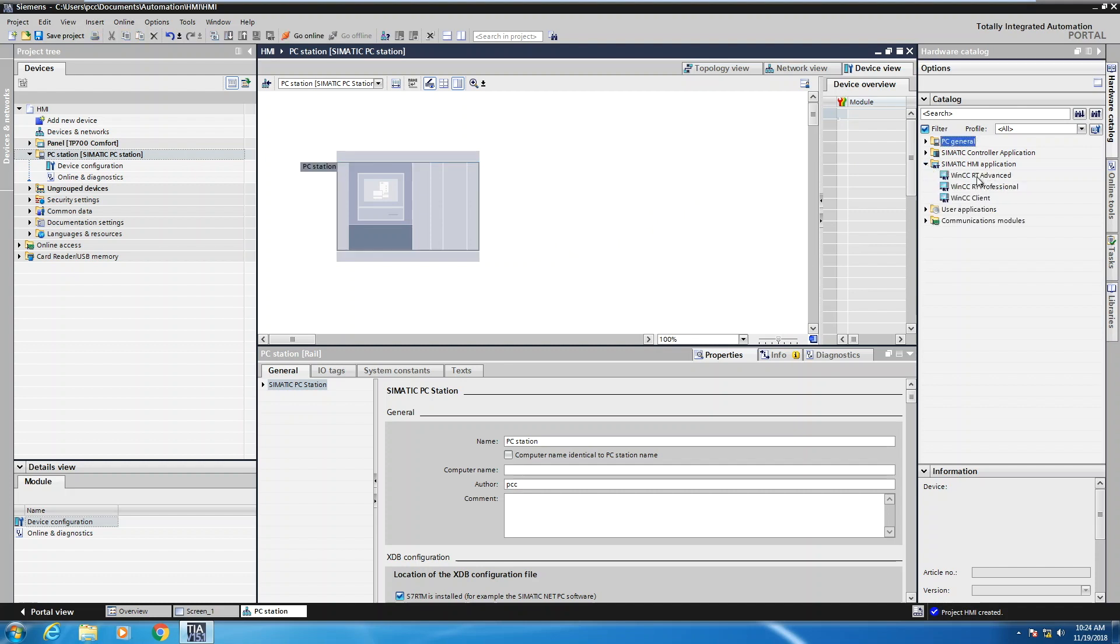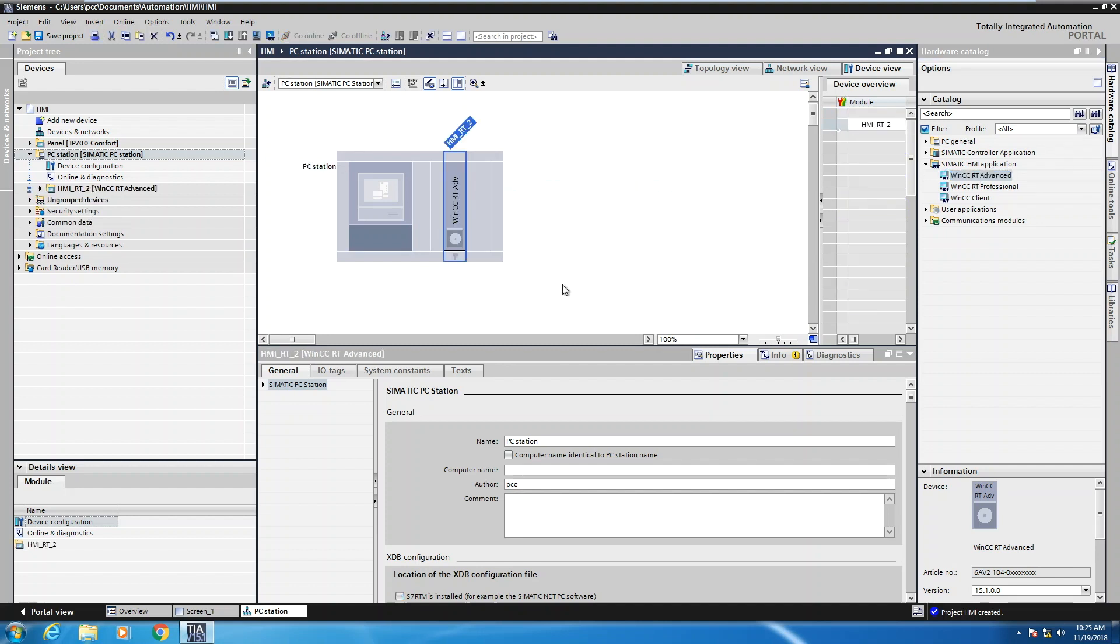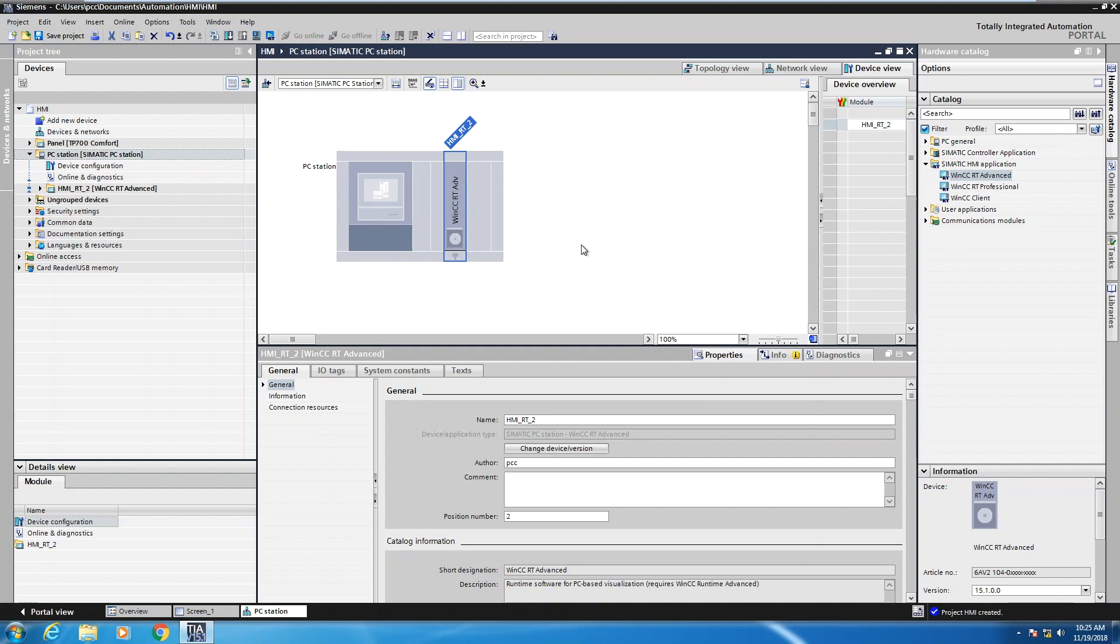And I really have two choices. I could pick RT advanced or I could pick RT professional. RT advanced is HMI on a PC. RT professional will be for full-blown SCADA on a PC. So I'll select WinCC RT advanced and it shows you where that can be dropped in the PC station. So I'll just drag that over and now this PC station will be used for a PC runtime advanced application.